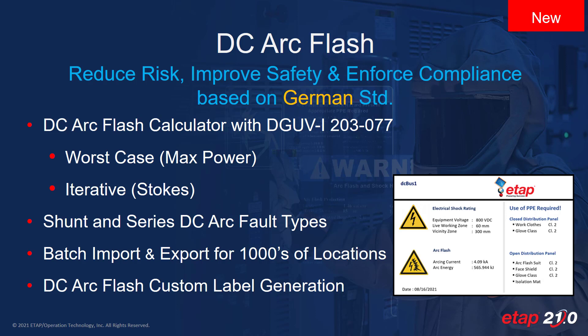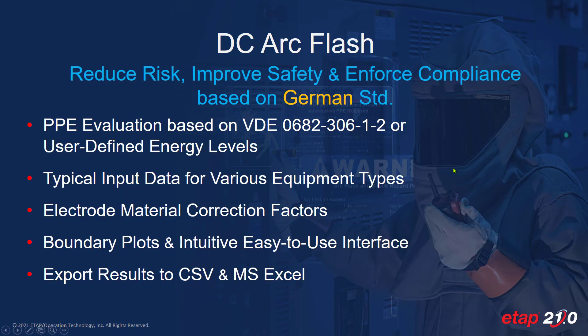Just like its Australian arc flash evaluation tool counterpart, the German DC arc flash calculator includes standard-specific arc flash labels. This tool also includes features to improve productivity and reduce data entry time. The German standard does not follow NFPA 70 PPE requirements but follows instead IEC PPE standards like VDE 06823061-2.